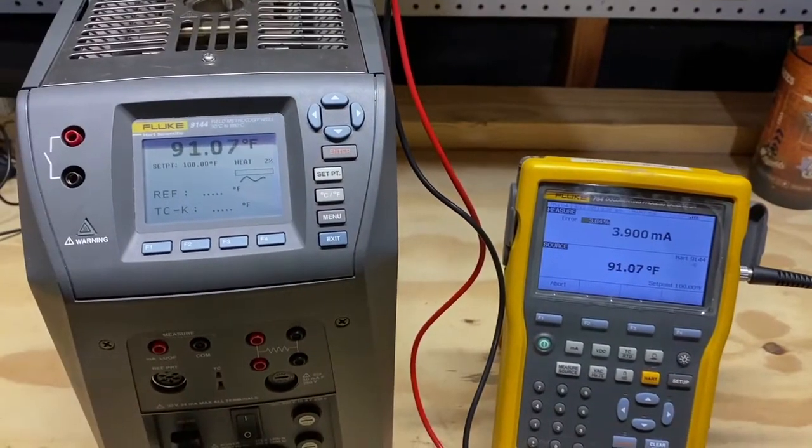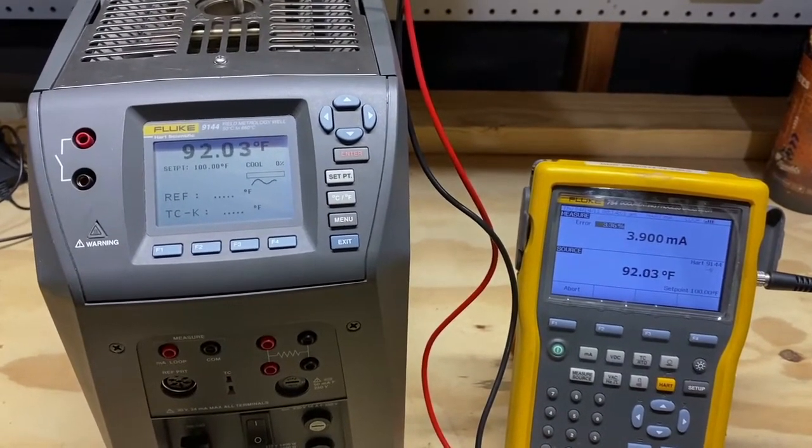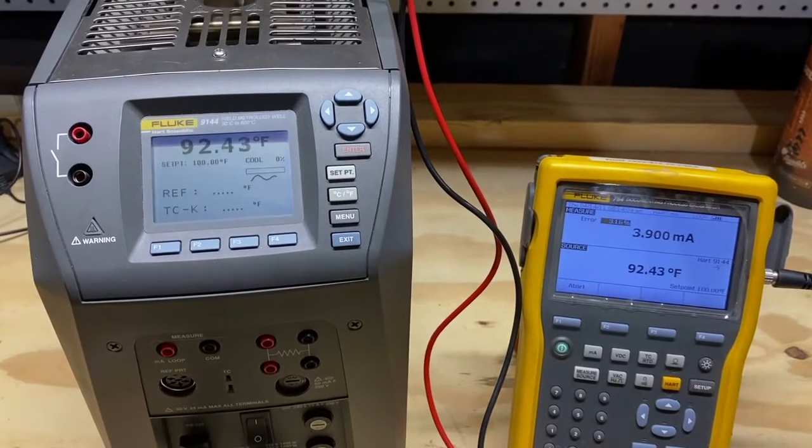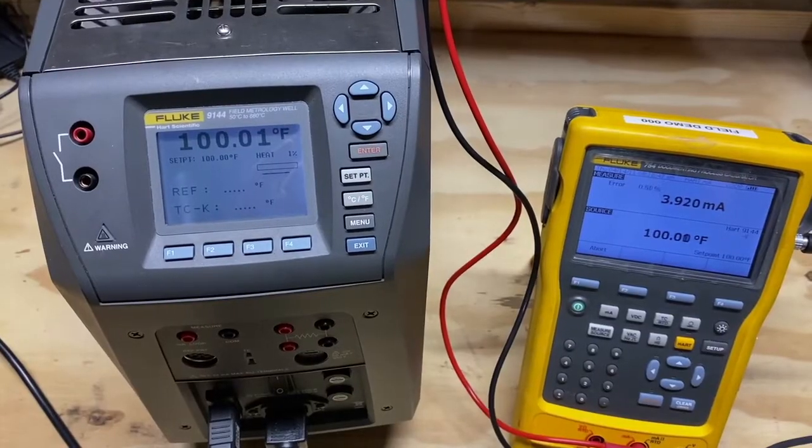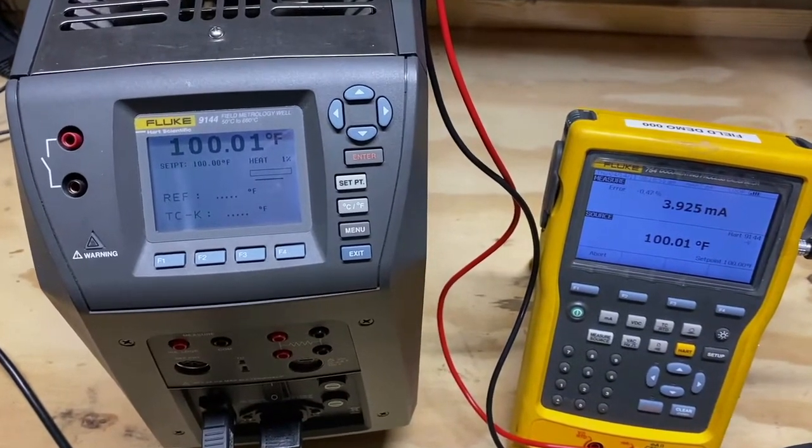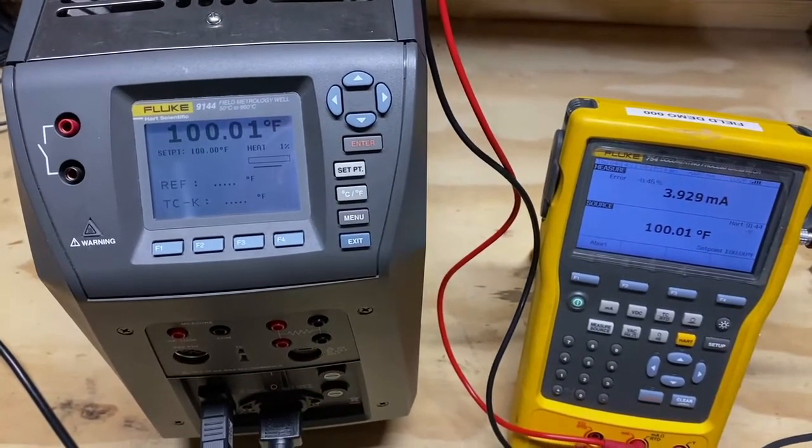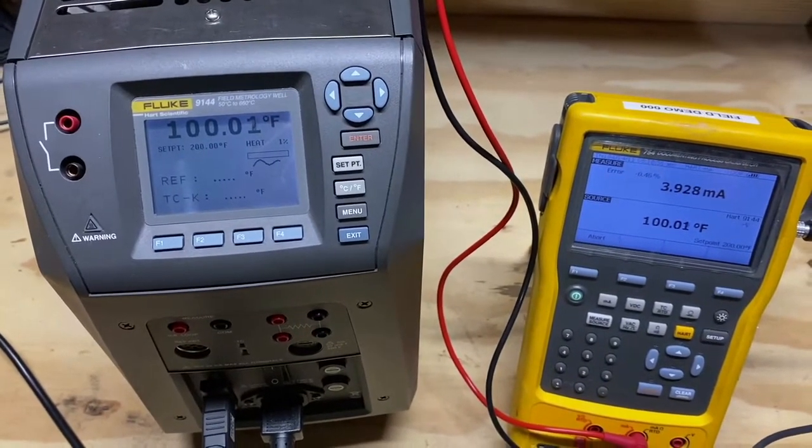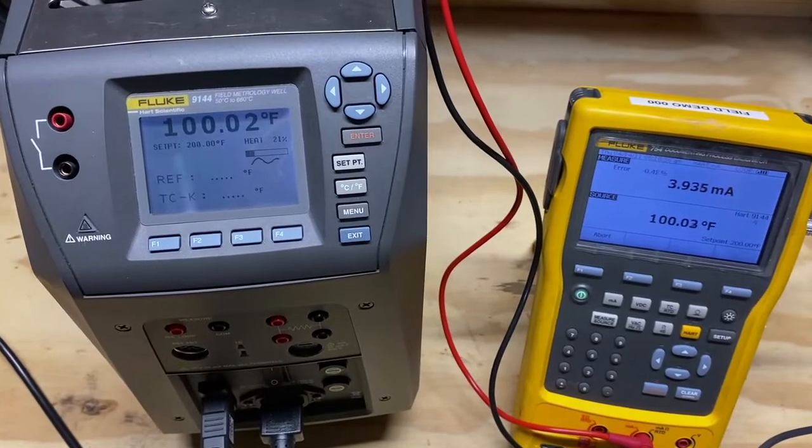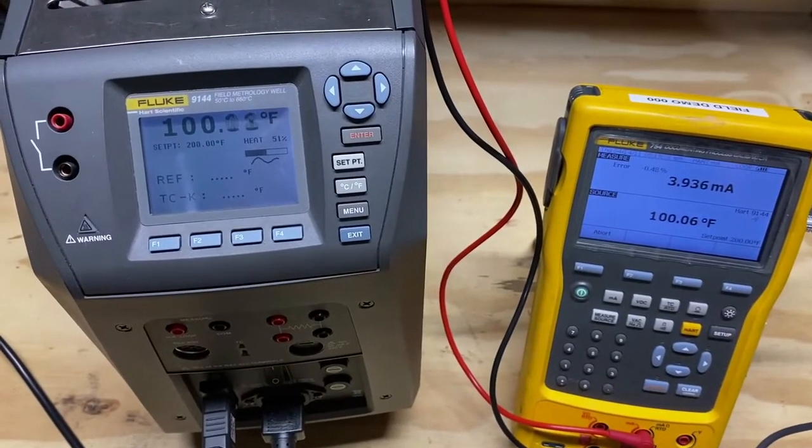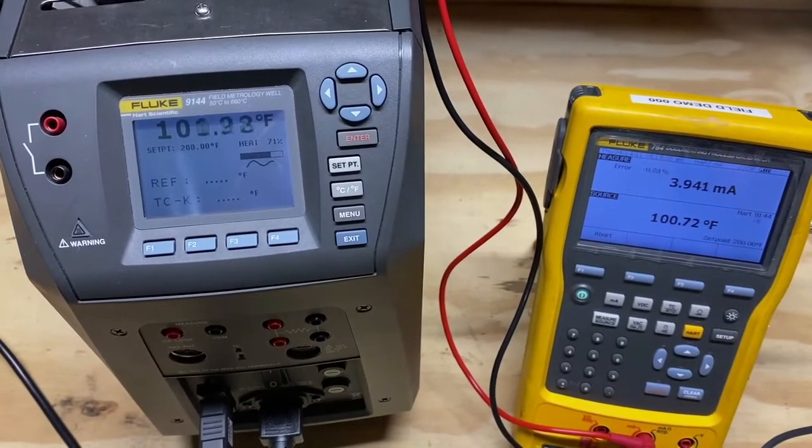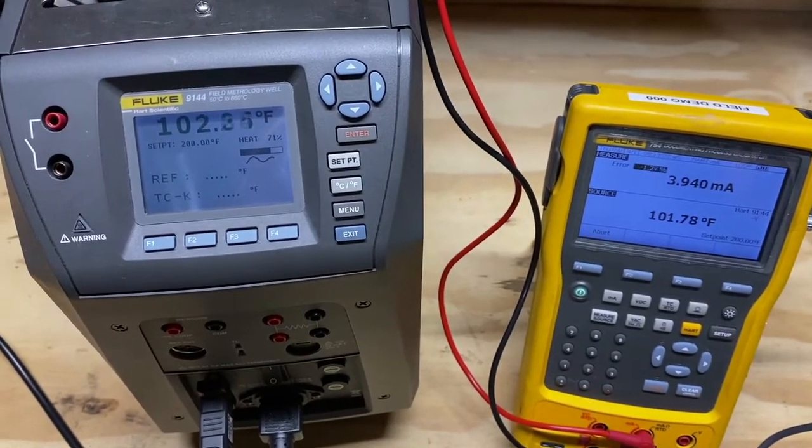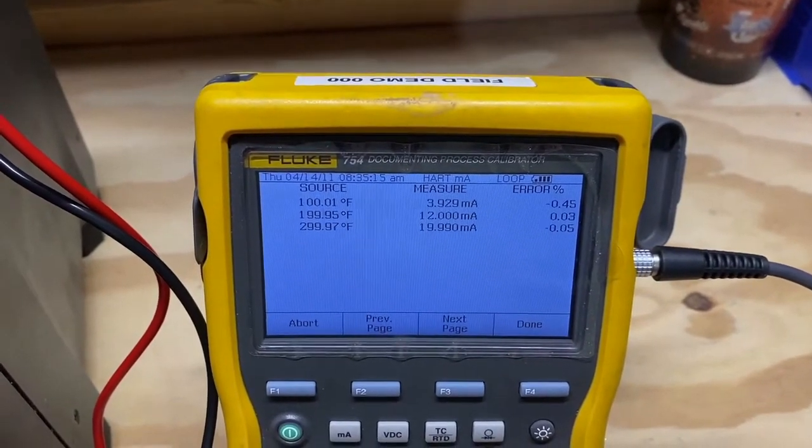After selecting auto test, the 9144 begins to heat to the first set point of 100 degrees Fahrenheit. Once the 9144 acclimates at its first set point of 100 degrees Fahrenheit, the 754 commands the 9144 to move to the next set point of 200 degrees Fahrenheit. This makes the service completely automatic and independent of a technician's need to accept a point and move to the next temperature point.